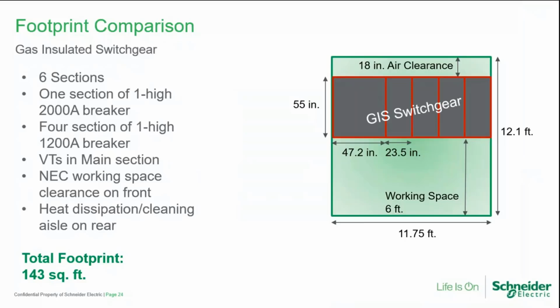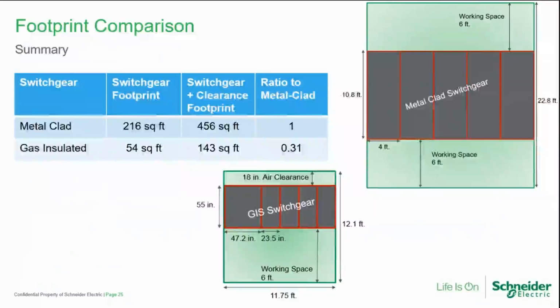If I do this with the gas insulated switchgear design, very similar, exactly the same one line layout, 2000 amp breaker main, four 1200 amp breaker feeders, VTs below the main, NEC working clearance in the front, and heat dissipation / cleaning aisle in the rear, looking at reducing that down to 143 square feet of space versus that 456 square feet with the metal clad. So a pretty big reduction there. So if we're comparing those two, metal clad versus gas insulated switchgear, looking at almost a 70% reduction in footprint. So some real big space savings here possible with a newer design of medium voltage switchgear.